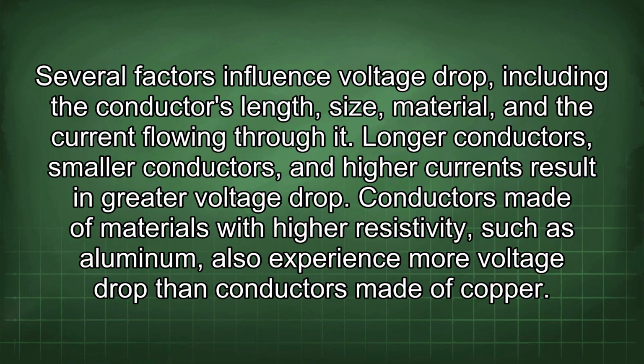Several factors influence voltage drop, including the conductor's length, size, material, and the current flowing through it. Longer conductors, smaller conductors, and higher currents result in greater voltage drop. Conductors made of materials with higher resistivity, such as aluminum, also experience more voltage drop than conductors made of copper.